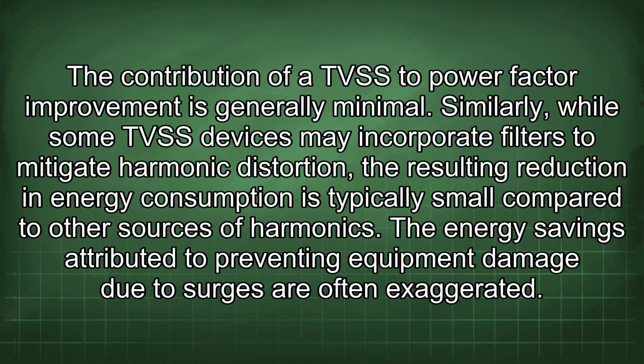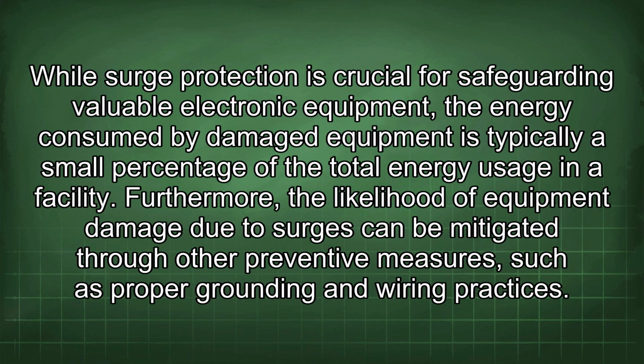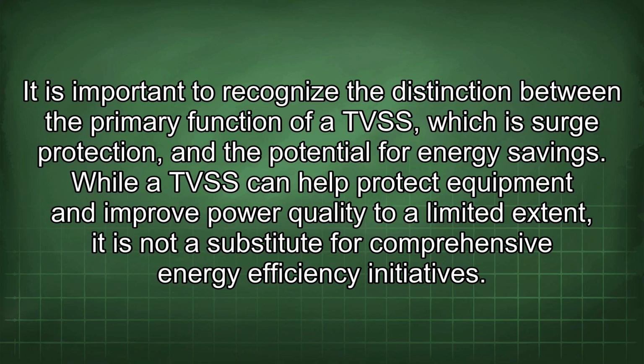The energy savings attributed to preventing equipment damage due to surges are often exaggerated. While surge protection is crucial for safeguarding valuable electronic equipment, the energy consumed by damaged equipment is typically a small percentage of the total energy usage in a facility. Furthermore, the likelihood of equipment damage due to surges can be mitigated through other preventive measures such as proper grounding and wiring practices. It is important to recognize the distinction between the primary function of a TVSS, which is surge protection, and the potential for energy savings. While a TVSS can help protect equipment and improve power quality to a limited extent, it is not a substitute for comprehensive energy efficiency initiatives.